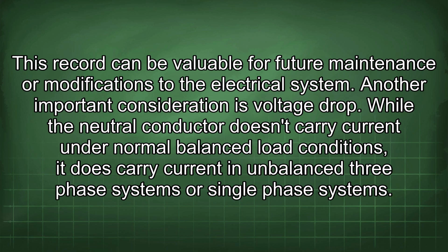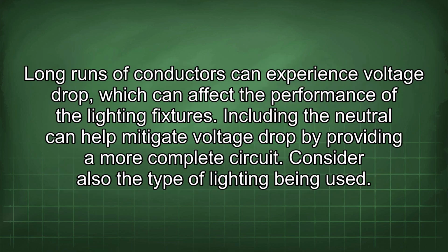While the neutral conductor doesn't carry current under normal balanced load conditions, it does carry current in imbalanced three-phase systems or single-phase systems. Long runs of conductors can experience voltage drop, which can affect the performance of the lighting fixtures. Including the neutral can help mitigate voltage drop by providing a more complete circuit. Consider also the type of lighting being used.